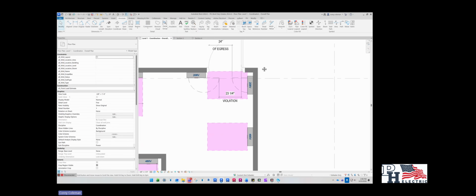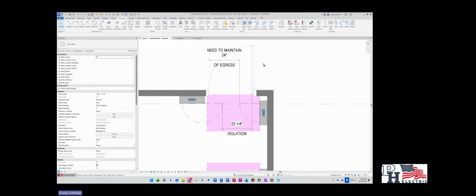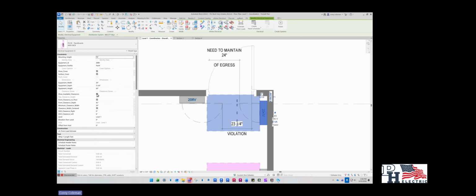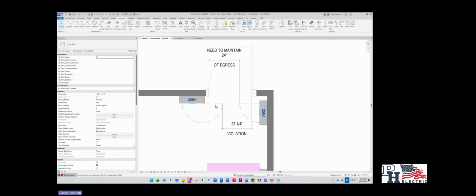Awesome. And then one of the other things that you have to consider is going to be the door swing as well as the egress. This is one that is usually missed a lot, but let me turn off the clearance here. Consider the door swing. If there is a door on the panel that swings open, you have to maintain at least 24 inches of egress so that a person can pass through it.